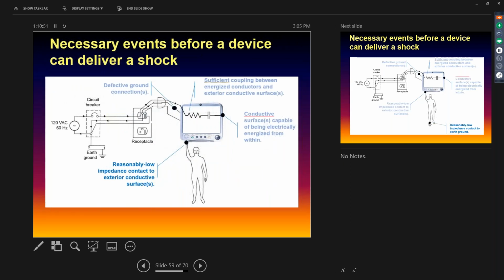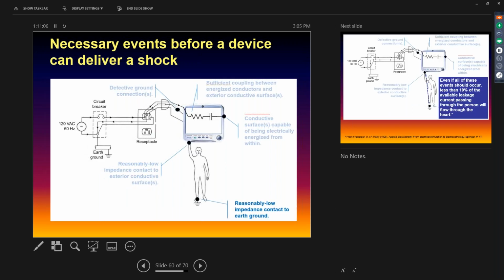Fourth thing we have to have is Joe Person, or nurse, staff, patient, whatever, has to have a reasonably low impedance connection between that exterior case or some point on that device, and then they have to be part of the circuit. Remember, like that very first slide we had, in order for any current to flow through a human being, they have to be physically, electrically part of the circuit. So not only do they need a low impedance connection at the box, the device, but they also have to be grounded.